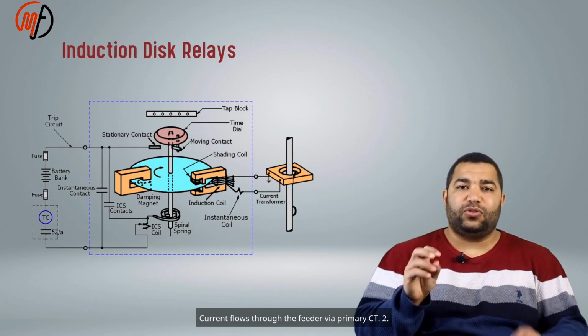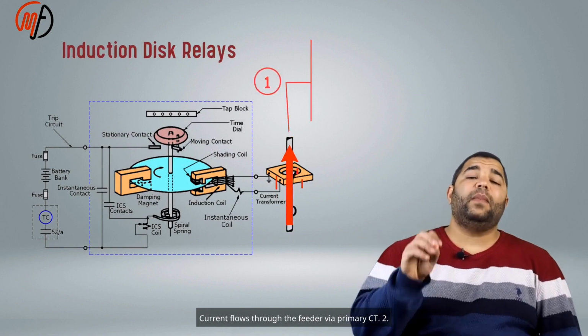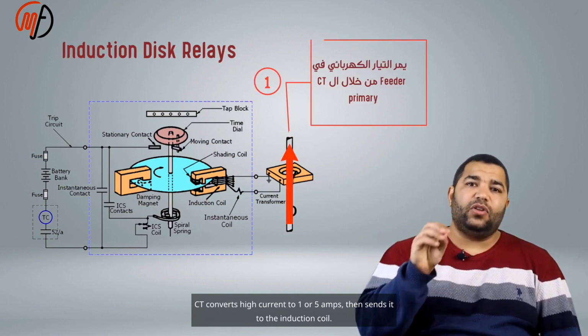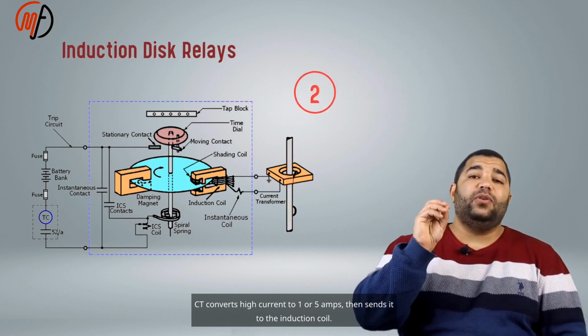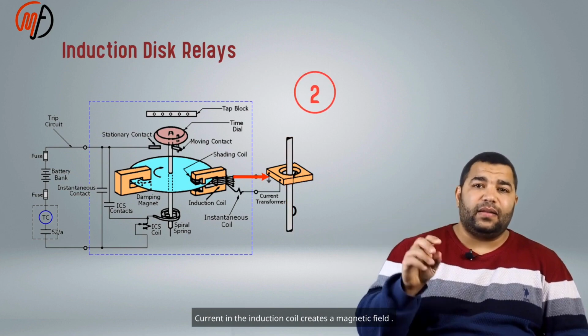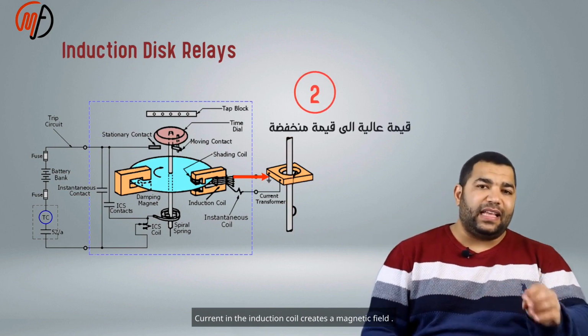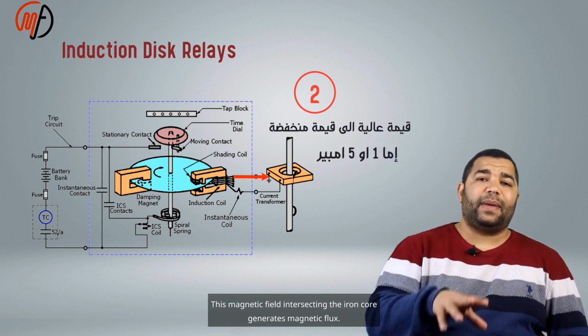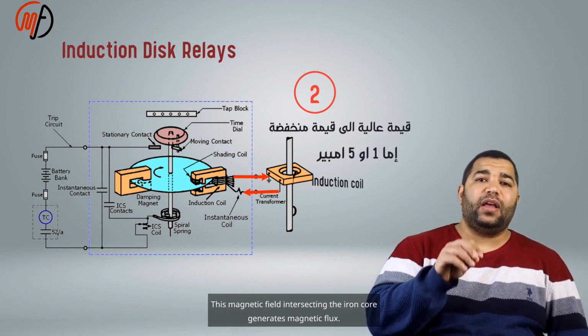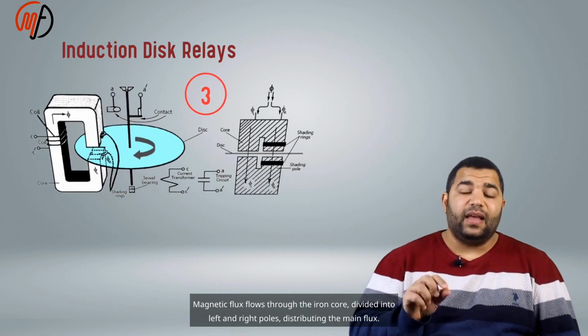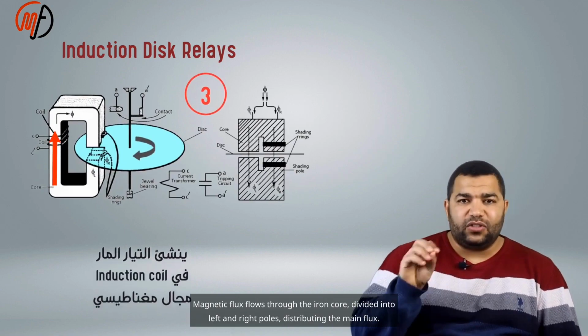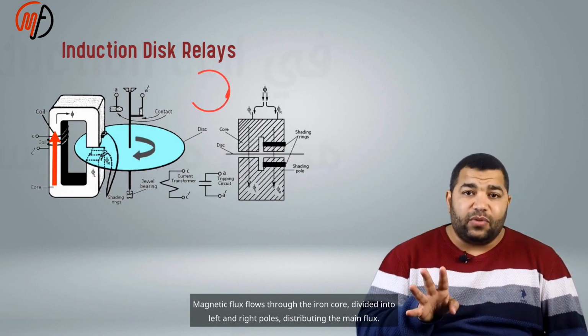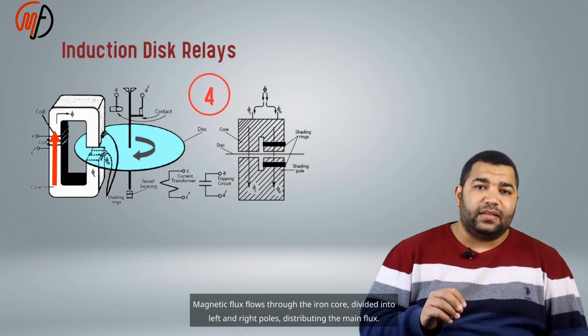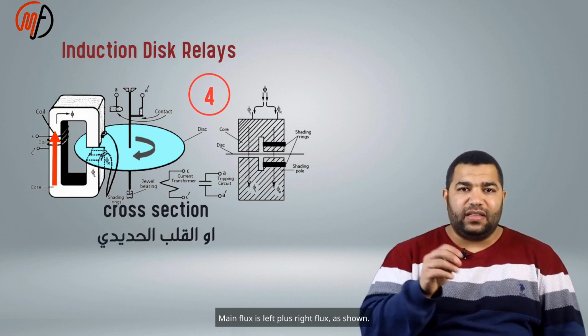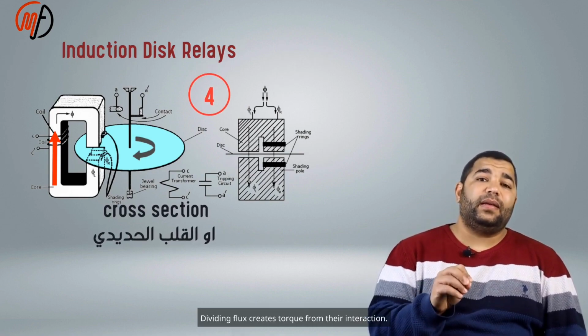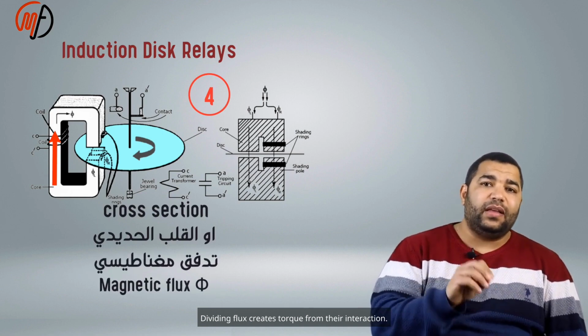1. Current flows through the feeder via the primary CT. 2. The CT converts high current to 1 or 5 amps, then sends it to the induction coil. 3. Current in the induction coil creates a magnetic field. 4. This magnetic field intersecting the iron core generates magnetic flux. 5. Magnetic flux flows through the iron core, divided into left and right poles, distributing the main flux. Main flux is left plus right flux, as shown. 6. Dividing flux creates torque from their interaction.